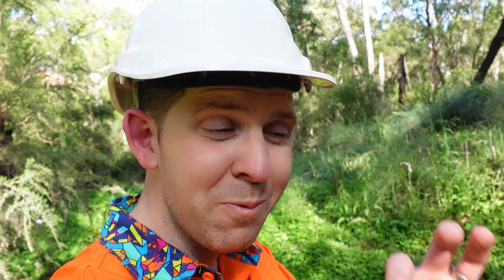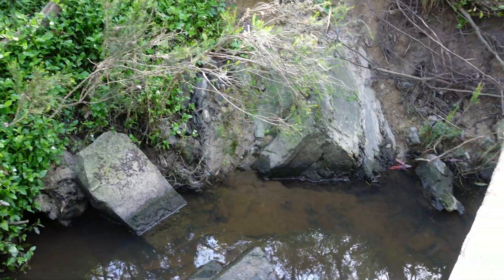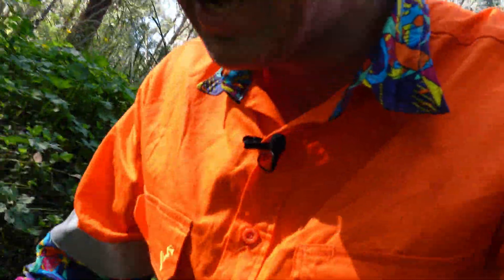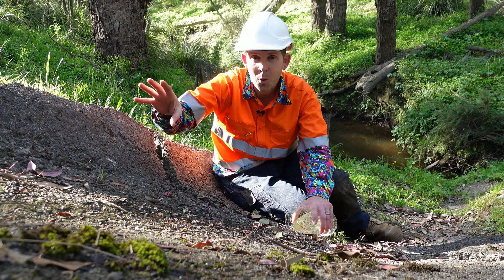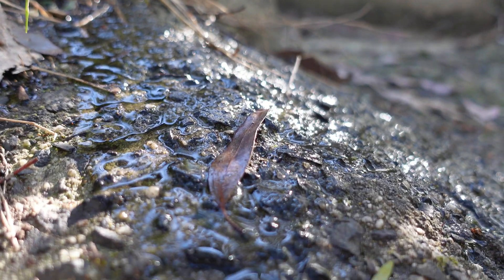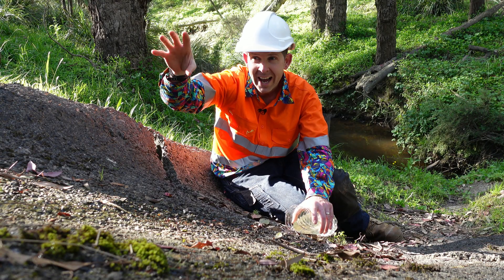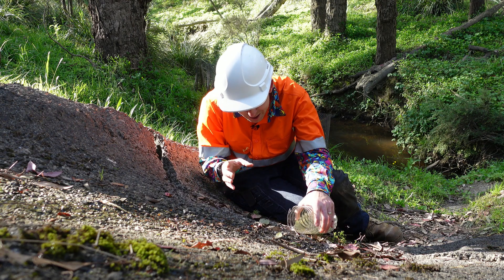This is my local creek, and it is absolutely swarming with mosquitoes after the amount of rain we've had. It's here where I'm searching for one of the most elusive of water creatures there is — the leak. Found a spoon drain and it looks like it's got a bit of a trickle of water coming down it. This is a stormwater drain that goes into the creek, and you can see how dry it was at the actual pipe, but then to the side there was just a small amount of water trickling down the outside. Water leaks that happen in the network actually tend to find the path of least resistance, and that's usually around pipes that already exist.